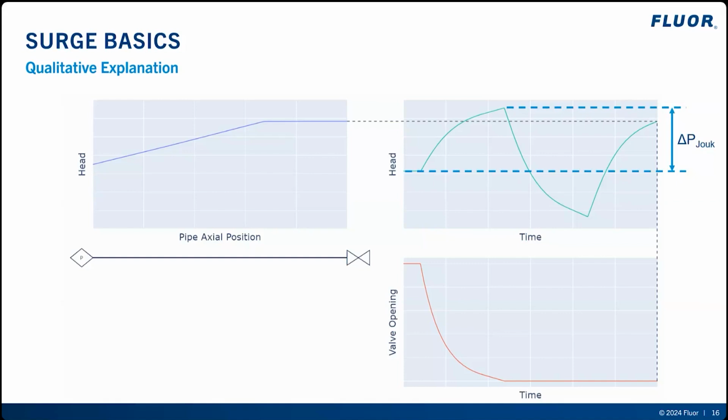Interestingly, the value of the low pressure wave can also be estimated as the negative Joukowsky pressure if one ignores losses due to friction. This is potentially important as, if the pressure in the fluid drops to the vapor pressure of the liquid, cavitation, or the partial vaporization of the fluid in the pipe can occur. In the worst case, this can lead to the liquid separating within the pipe, with a vapor space created in between, known as column separation. Sudden collapse of this large volume of vapor can cause significant velocities in the liquid, with subsequent pressure waves ensuing.